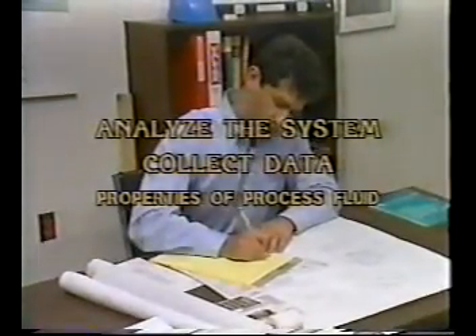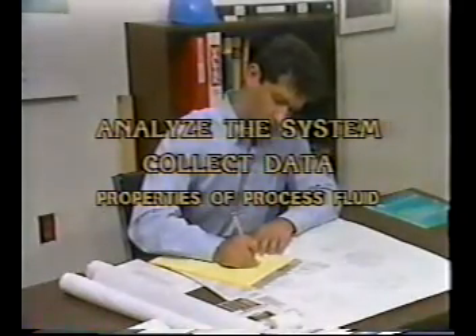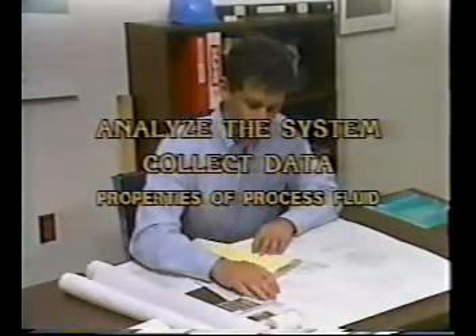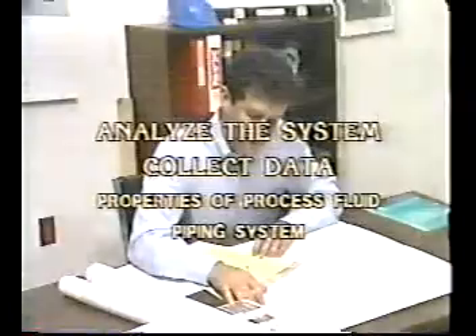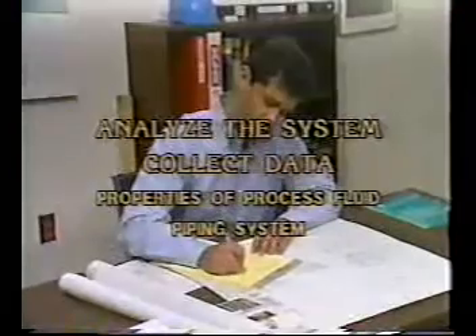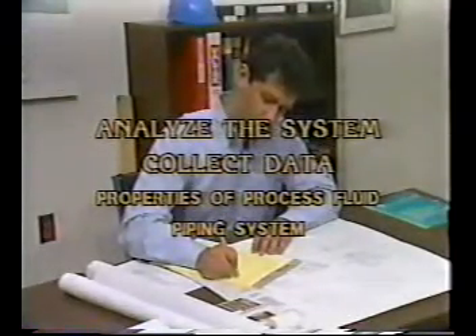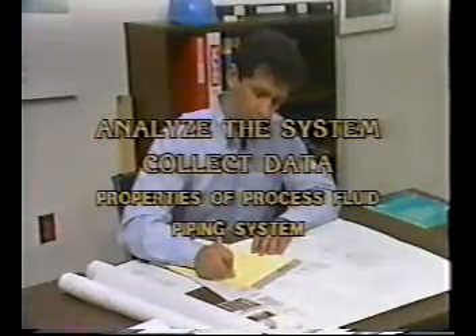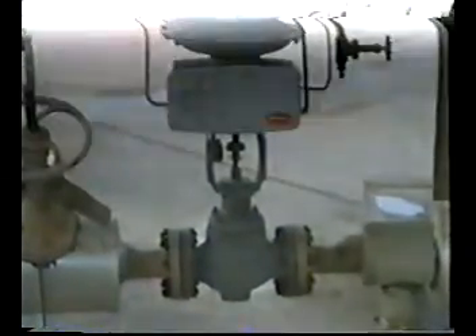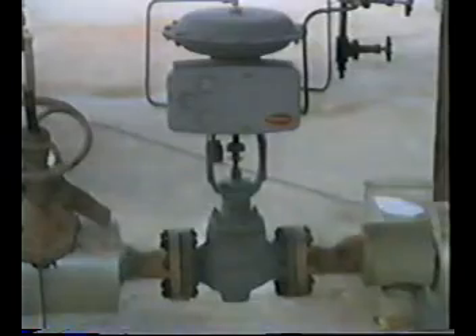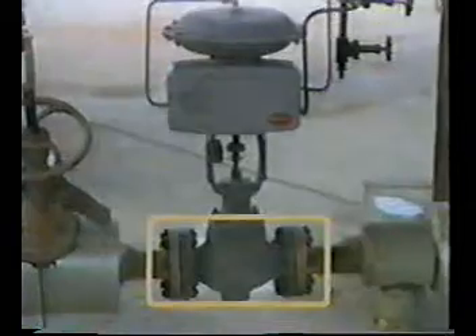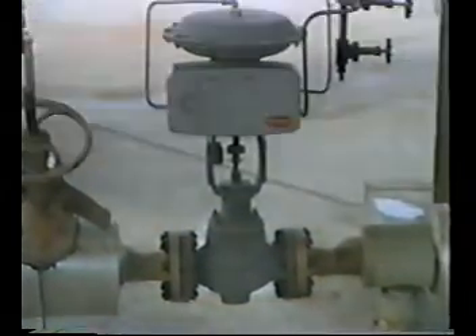Properties of the process fluid aren't the only concern when selecting a valve. It's important to gather information about the piping system. One reason is that the control valve must conform to the applicable piping code. It's also necessary to ensure physical compatibility between the system piping and the valve, so you need the piping specifications. For example, do the specifications call for flanged, welded, or threaded joints? Are the pipes to be lined or unlined?